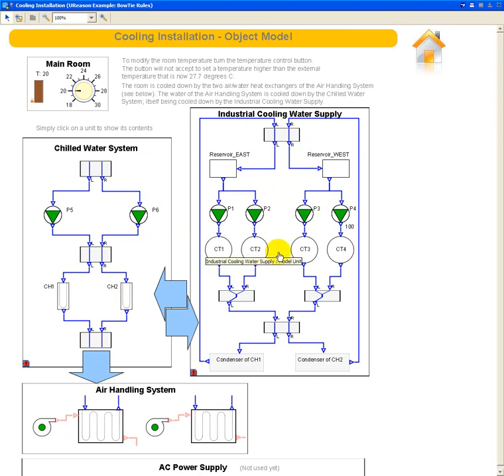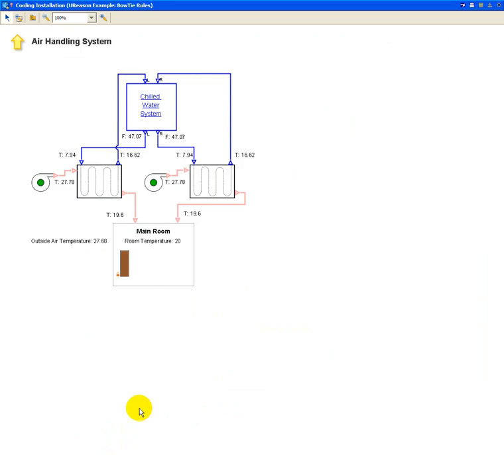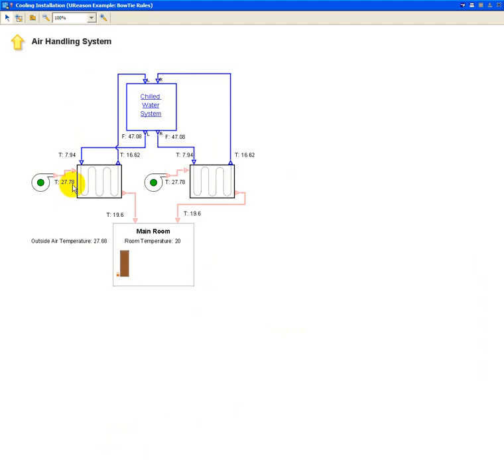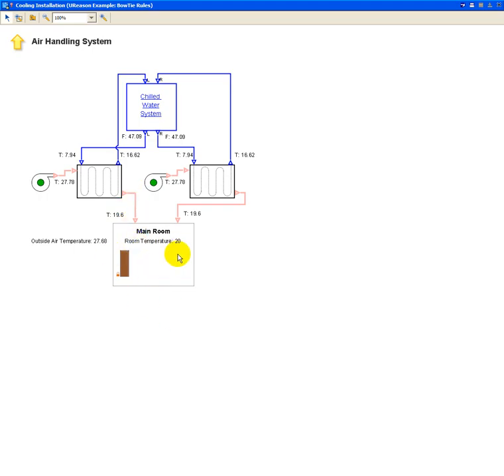Each of these units can be clicked, so I can click on the air handling system and go inside this unit and see that it consists of two fans blowing air into these heat exchangers. You can see the input temperature, 27.78 degrees, being cooled down to almost 20 degrees here, and going inside this room where the actual temperature is exactly 20 degrees.